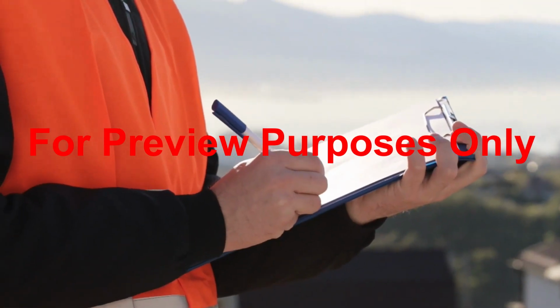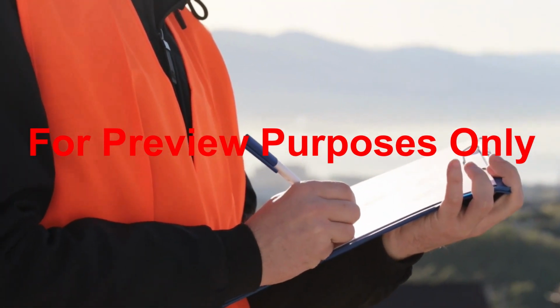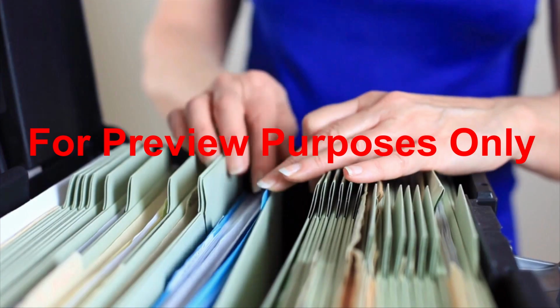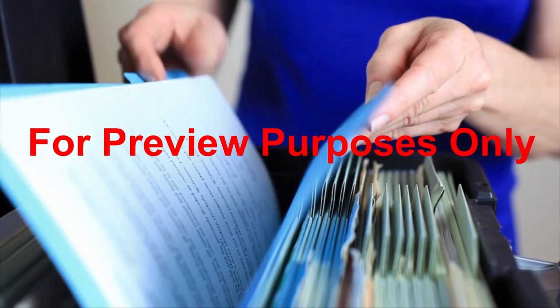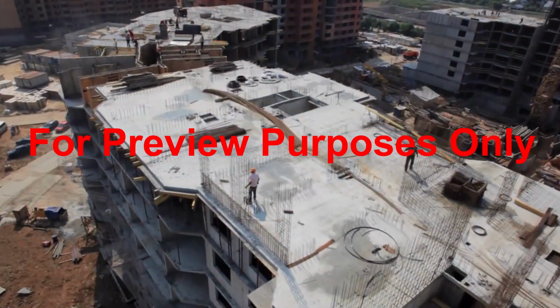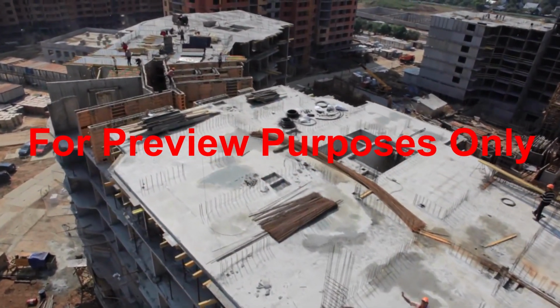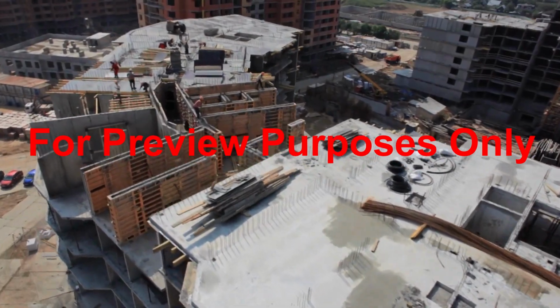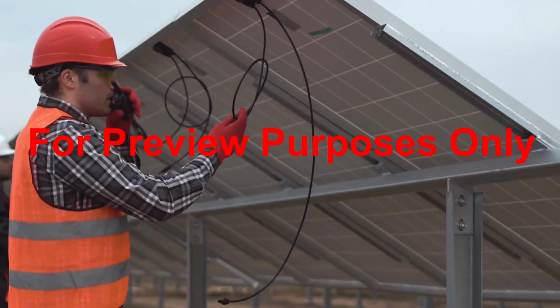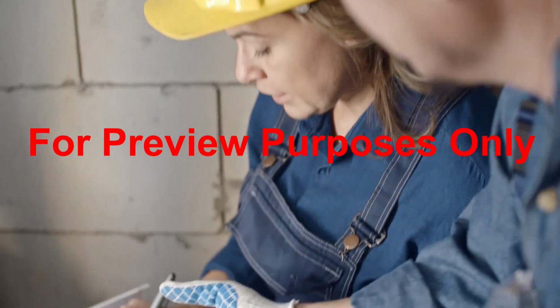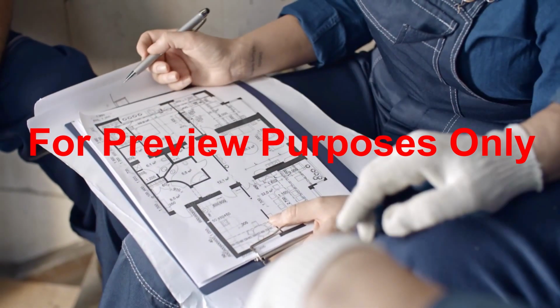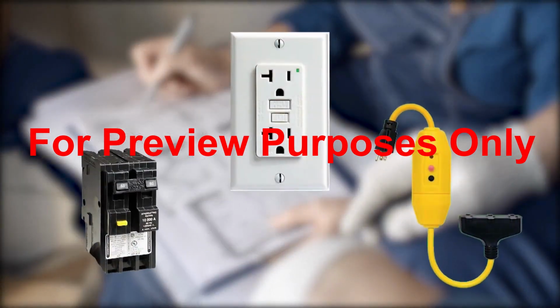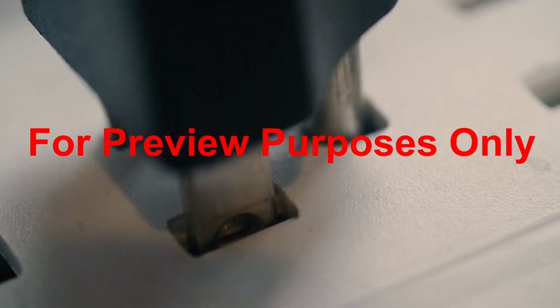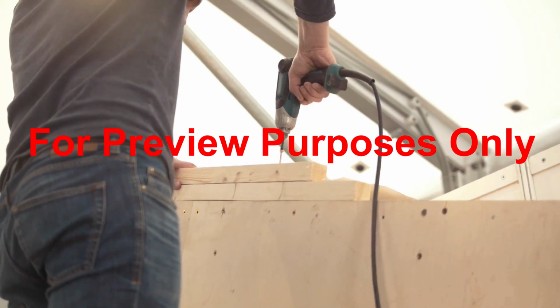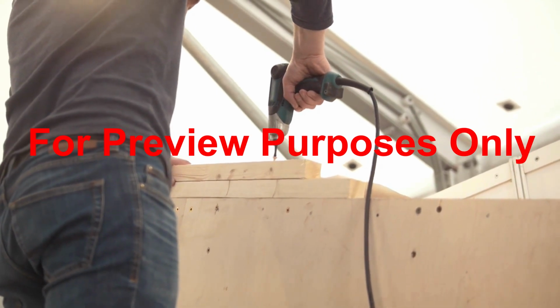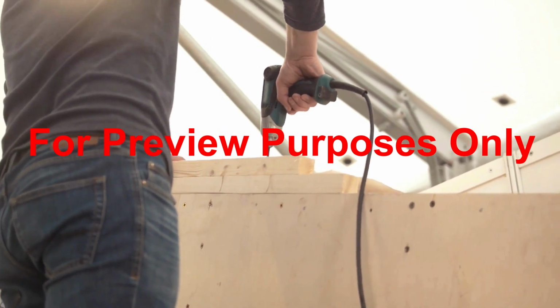OSHA regulations require a copy of the written Assured Grounding Program to be available on the worksite and records of the continuity testing to be maintained as well. In some situations, however, it may not be possible to ensure proper grounding on a worksite. So as an alternative to an Assured Grounding Program, OSHA also allows construction employers to equip their job sites with ground fault circuit interrupters. An important advantage of GFCIs is that they can perform their safety function even when a continuous ground connection is not available.